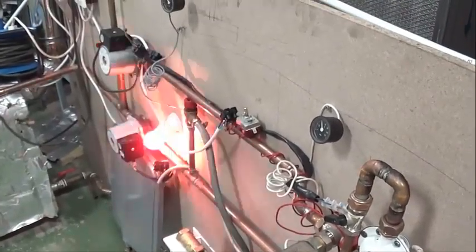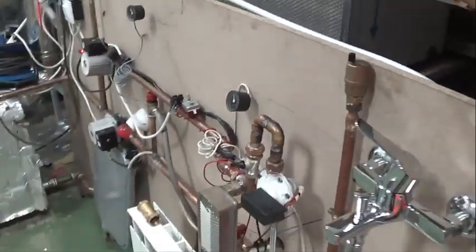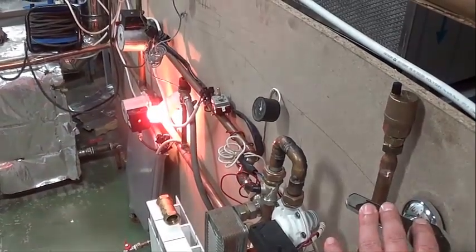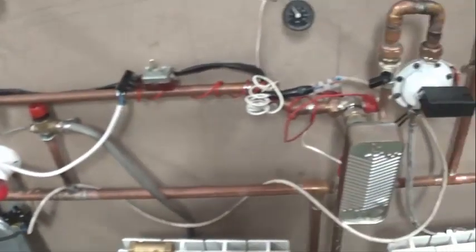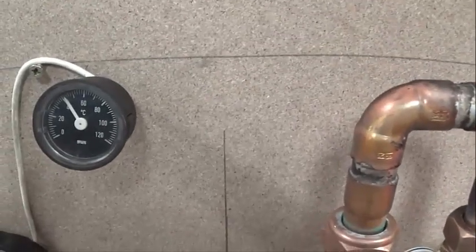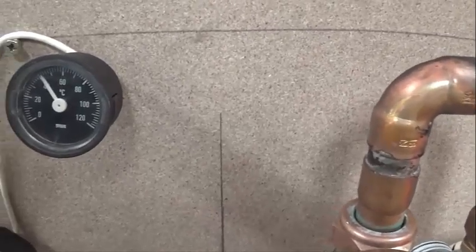See, I want to show it at the tap — how I open and how I close. What do we see? The sanitary hot water activates. Now the water has been cut off; it returns to the temperature we set at 90 degrees. And here we are measuring a range in the hot water — the cold was at 25 degrees and here it is at 42 degrees.